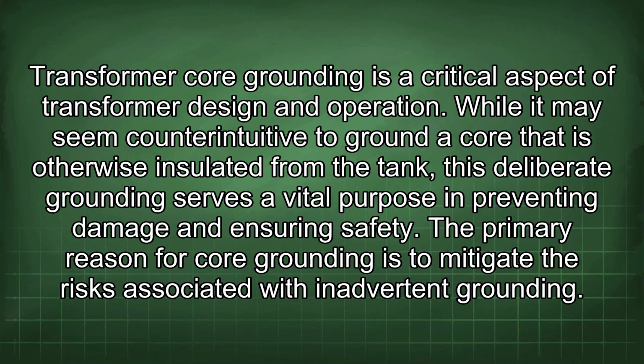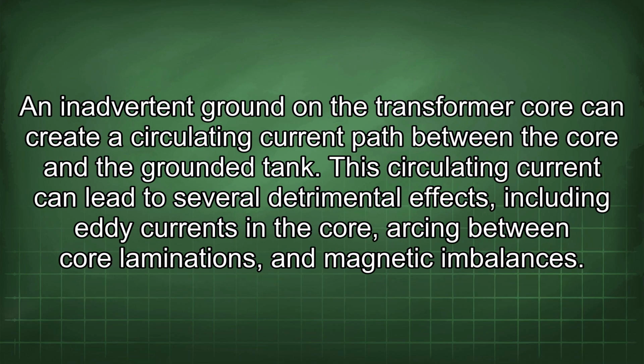Transformer core grounding is a critical aspect of transformer design and operation. While it may seem counterintuitive to ground a core that is otherwise insulated from the tank, this deliberate grounding serves a vital purpose in preventing damage and ensuring safety. The primary reason for core grounding is to mitigate the risks associated with inadvertent grounding. An inadvertent ground on the transformer core can create a circulating current path between the core and the grounded tank.